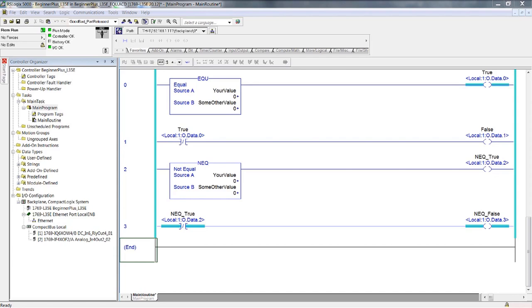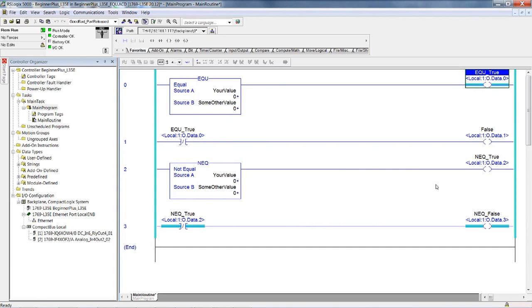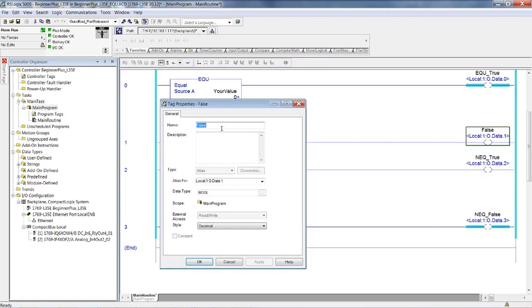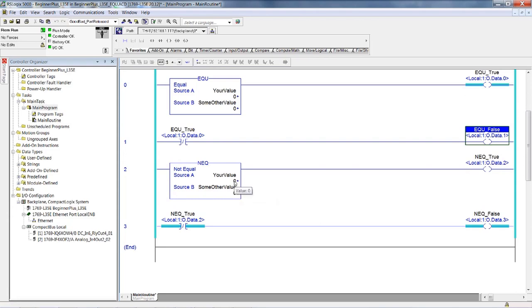If you want to edit the aliases for the tags used in the equal instruction rungs: right-click, edit — remember you're not creating a new tag, you're editing an existing tag. That's allowable online because you're not changing the structure of memory; you're simply changing the text of the pointer that points to that particular memory address. Try changing the values. Grab your value and type in 5 — now the not-equal is true and the equal is false, because 5 is not equal to 0.